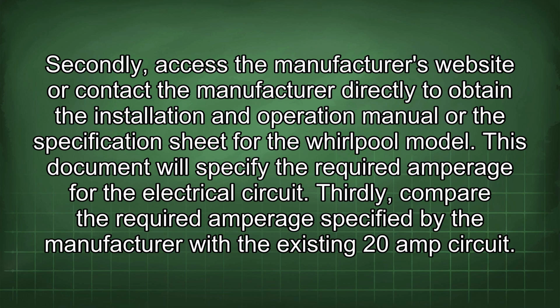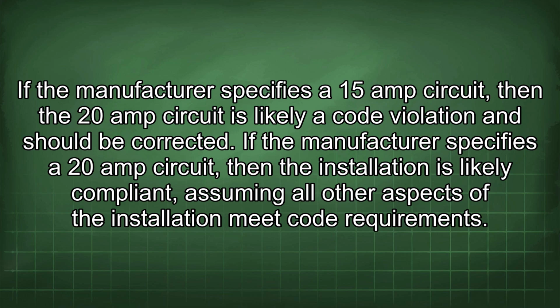Thirdly, compare the required amperage specified by the manufacturer with the existing 20 amp circuit. If the manufacturer specifies a 15 amp circuit, then the 20 amp circuit is likely a code violation and should be corrected. If the manufacturer specifies a 20 amp circuit, then the installation is likely compliant, assuming all other aspects of the installation meet code requirements.